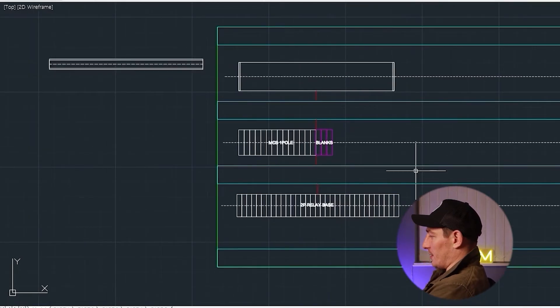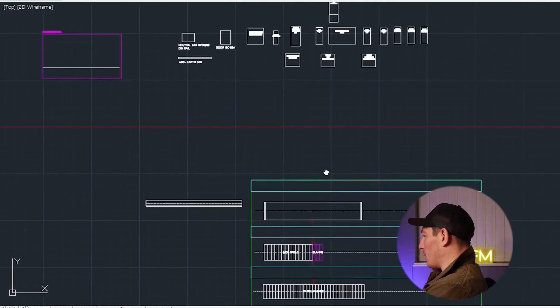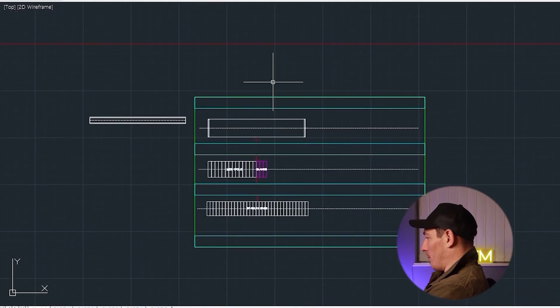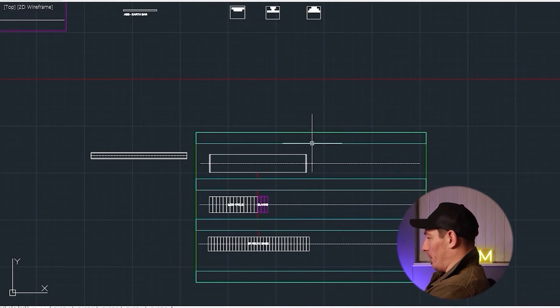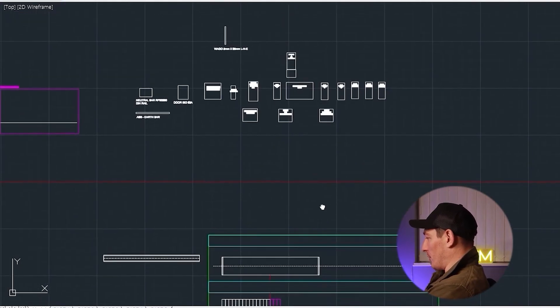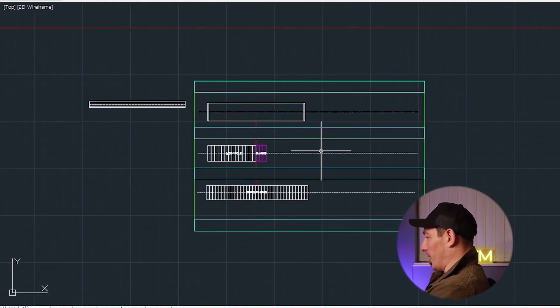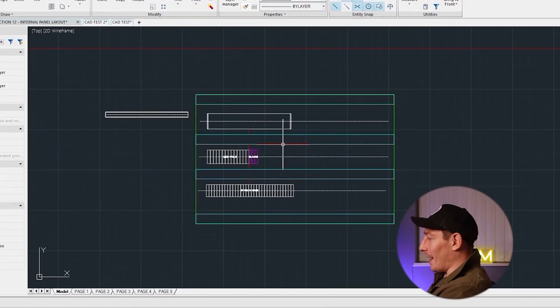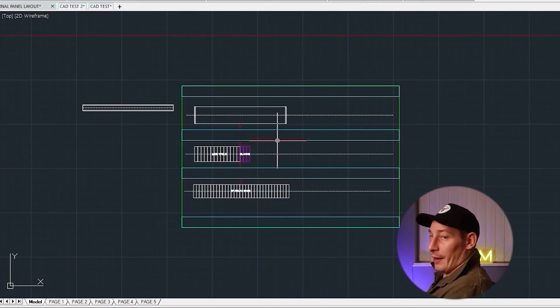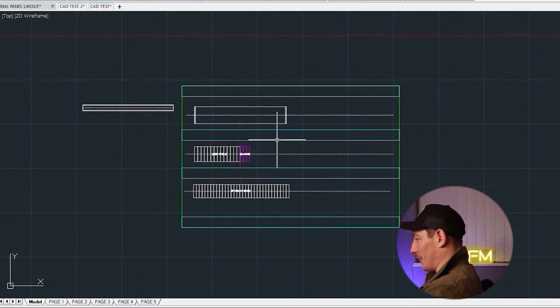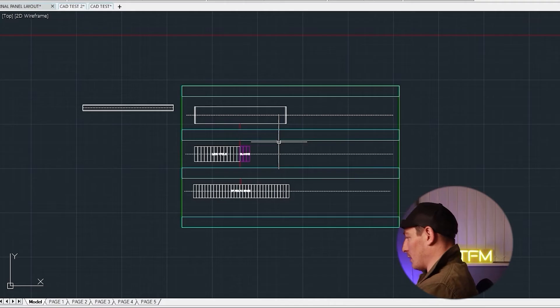I've just extended the center lines of the din rail, so looking at that now I'm pretty confident that all of those components are gonna fit in there. Now it doesn't have to be spaced perfectly and in a logical order at the moment, but it's just to try and get an idea that that control panel is gonna be the right size. So I'll quickly add that all now and then we come back to assess what it looks like.